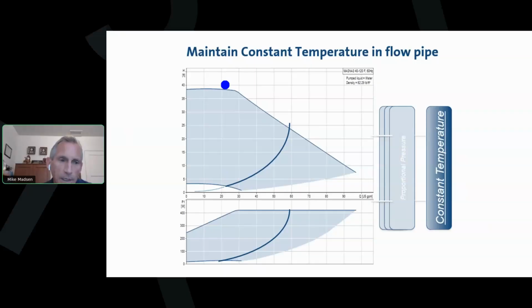The second control mode would be to maintain constant temperature. So what we're doing with distributed pumping, we're replacing those control valves with a smart pump. We're taking a leaving air temperature sensor from the air handler, and we're sending that directly to the smart pump. So now the smart pump is working like a control valve, and if we need more chilled water through the coil or less chilled water through the coil, it's just going to speed up and slow down based on that leaving air temperature sensor. That does follow a square function, that control curve. So you can see here at max flow, I can't see my screen, it's behind my picture for me. I think from memory, it's about 58 gallons per minute at 23 feet of head.